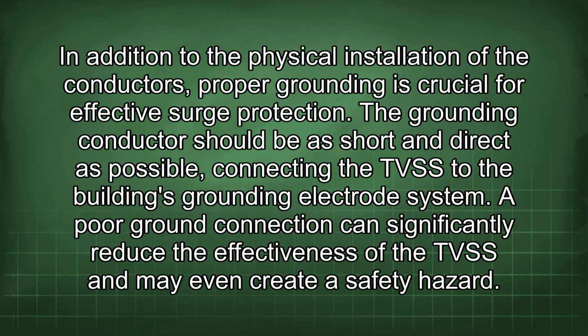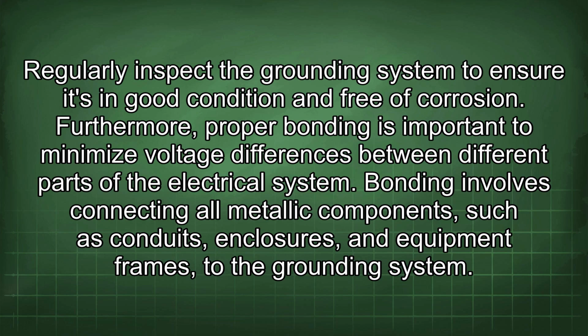In addition to the physical installation of the conductors, proper grounding is crucial for effective surge protection. The grounding conductor should be as short and direct as possible, connecting the TVSS to the building's grounding electrode system. A poor ground connection can significantly reduce the effectiveness of the TVSS and may even create a safety hazard. Regularly inspect the grounding system to ensure it's in good condition and free of corrosion.